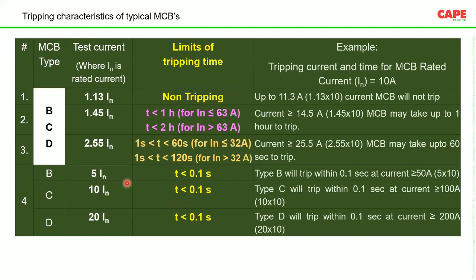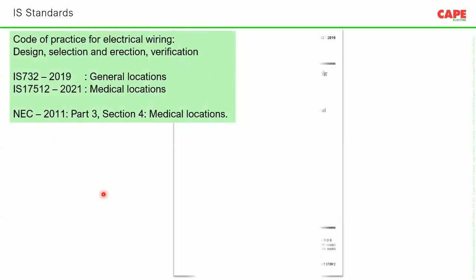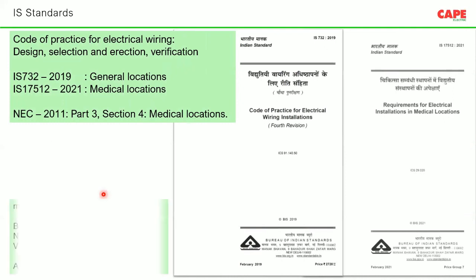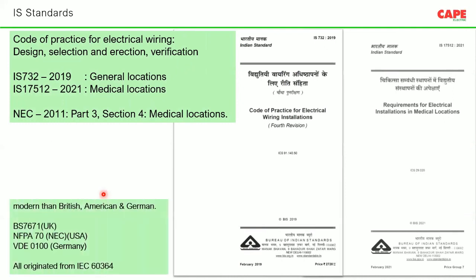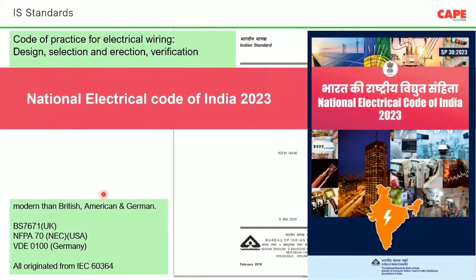So if you use a stabilizer, the problem is the instantaneous tripping, or sometimes 2.55 times the nominal current. These calculations are missing. As a result, the MCBs may take much more time to trip, ending up with a fire or an accident.